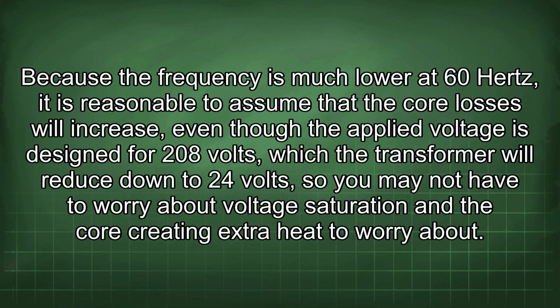Because the frequency is much lower at 60 Hz, it is reasonable to assume that the core losses will increase, even though the applied voltage is designed for 208 volts, which the transformer will reduce down to 24 volts, so you may not have to worry about voltage saturation and the core creating extra heat to worry about.